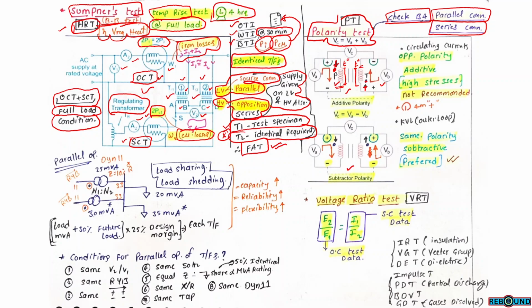So during the same time period, on both primary side and secondary side, the currents are entering in opposite directions. So the opposite polarities will appear on the windings. On the primary side, polarity is plus and minus. On the secondary side, the polarity is plus and minus. So during this period, as the currents are entering from opposite directions, circulating currents will flow in the windings, which cause very high stresses in the windings and insulations. So this is additive polarity.